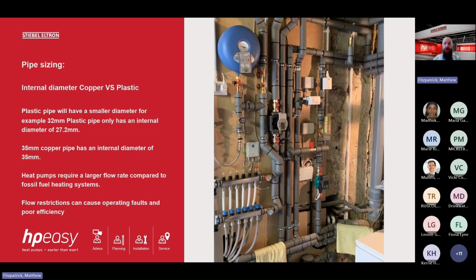Now, this can cause problems with flow rates, and it can also cause problems with flow velocity, which makes systems quite noisy. So we need to ensure we get the correct pipe diameter. For copper, the size that's given, so 28 mil or 35, is the internal diameter. So if you order 28 mil plastic, that could be 22 mil or 23 mil internal diameter. So you would need 32 mil plastic compared to 28 mil copper. If you do have flow restrictions, you can start to cause faults with the system. So we call them high pressure faults. It can't deliver the energy, and a noisy system. The volume is passing through the pipework too quick, creating excessive noise in the property.